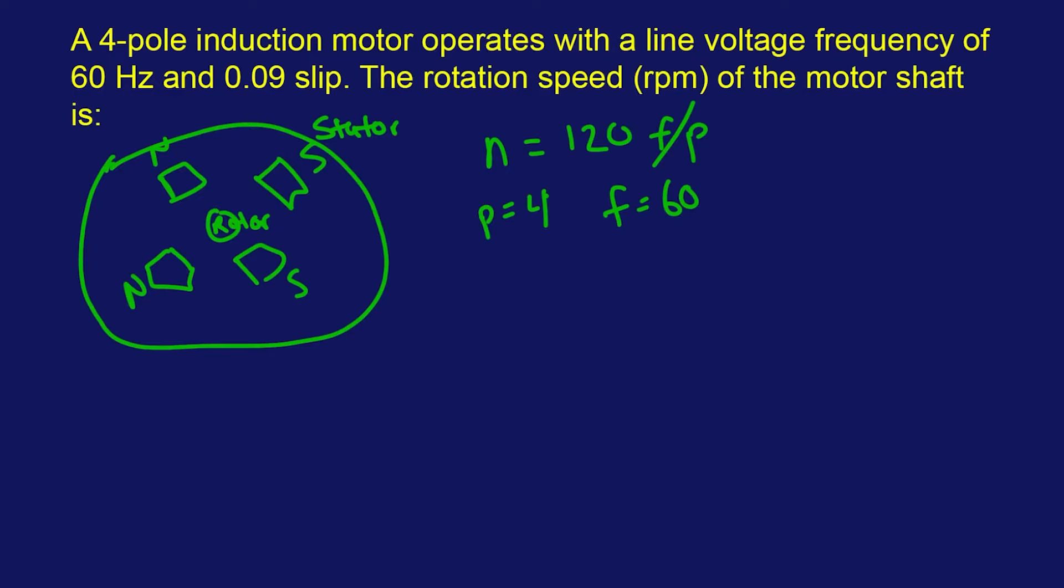So we're going to solve for the rotational speed of the motor or rotor, which is going to be 120 times 60 divided by four. That should be 180. No, 1800. I almost did it again where I messed up the calculation. And that's going to be the rotation of the motor, synchronous speed I should say, of the motor.